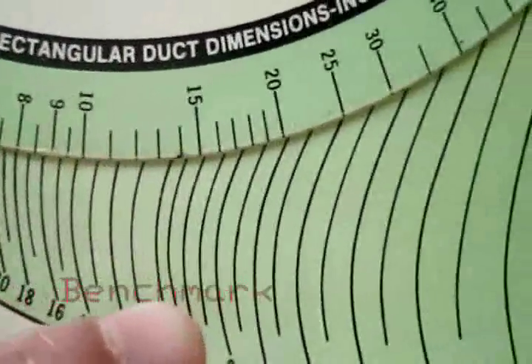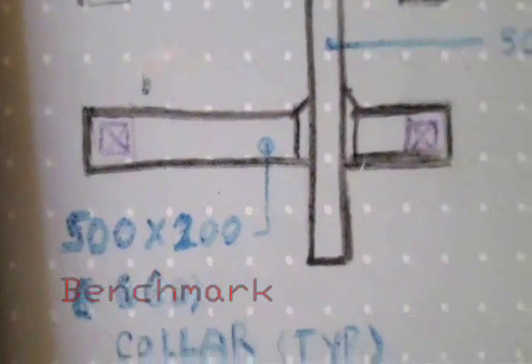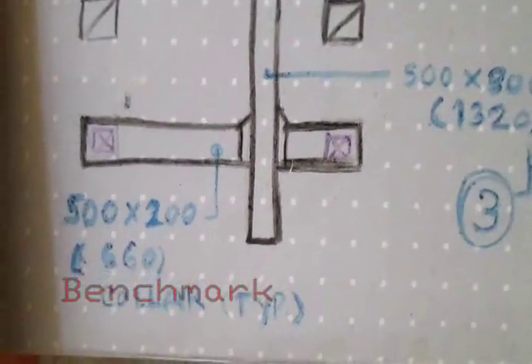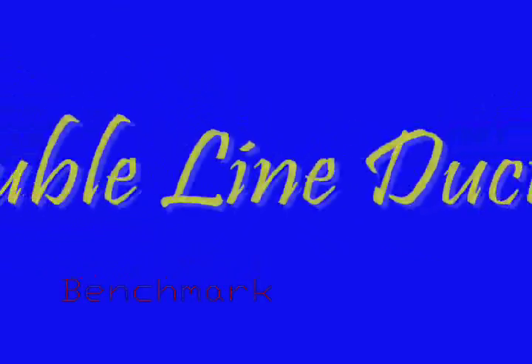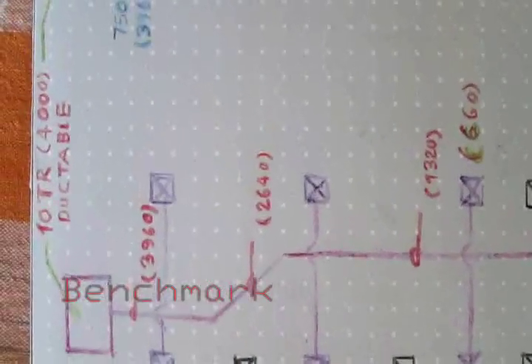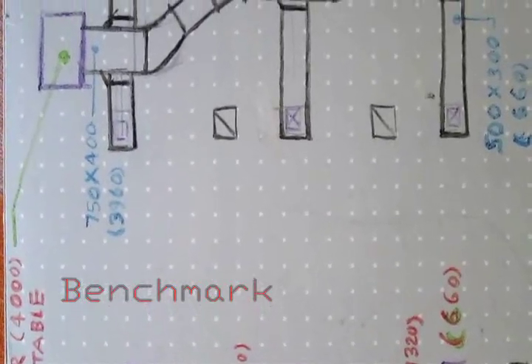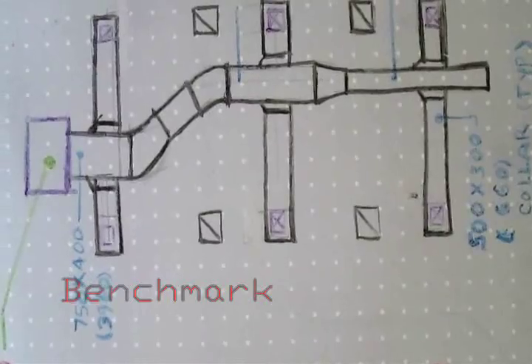For the second case, the collar size for 660 CFM at 0.1 friction gives approximately 667 CFM with a velocity of 600, which is acceptable. The duct sizes we are getting are 20 inch by 8 inch, that is 500mm by 200mm, because we have a diffuser size of 15 inch by 15 inch, which is around 375mm by 375mm.